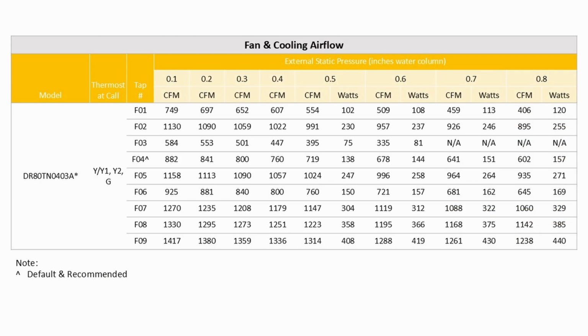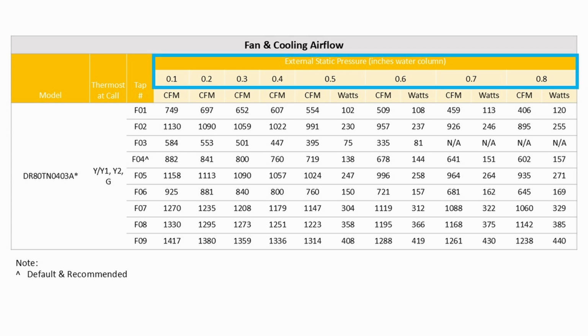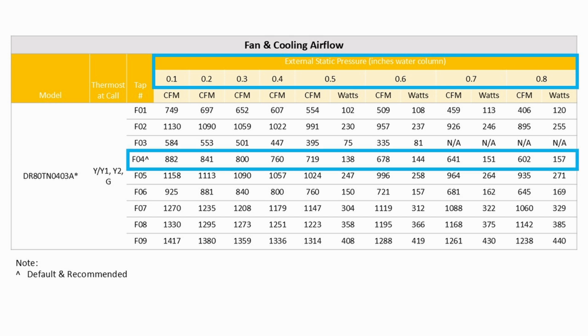Fan and cooling airflow. On the chart below, I've highlighted the top section that shows external static pressure in inches of water column from point 1 to point 8. I've also highlighted the default speed for the DR80TN, which is F04. I've done this to show the effect that external static pressure has on airflow CFM and watts of power used.